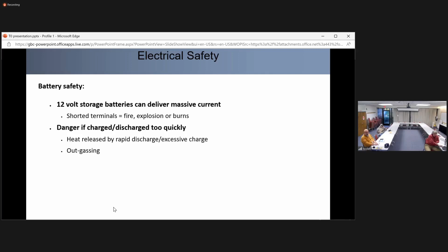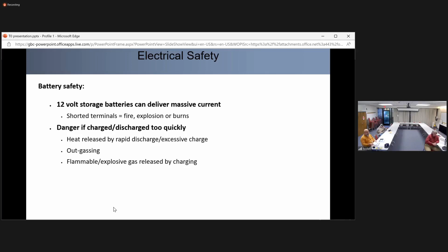Batteries also present dangers if they are charged or discharged too quickly. The reason is there's a lot of heat released by that rapid discharge or excessive charge, which can overheat the battery. When you overheat that battery, it causes something known as outgassing. The chemical reaction inside that cell generally produces hydrogen gas, a flammable, explosive gas released during charging. So when charging batteries of that type, they need to be in a ventilated place so you don't allow that explosive gas to accumulate.